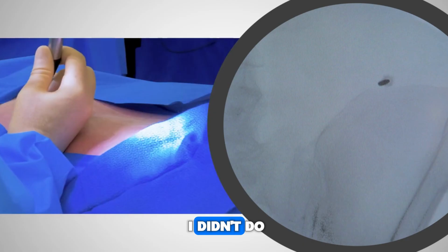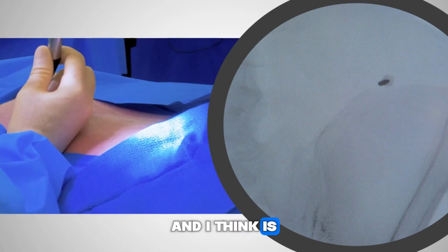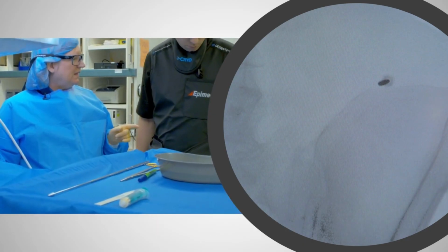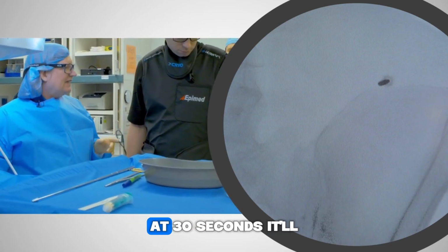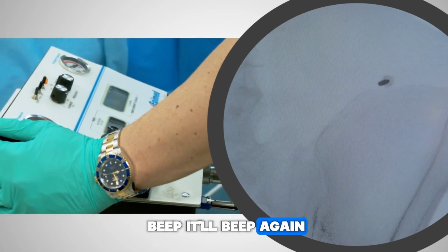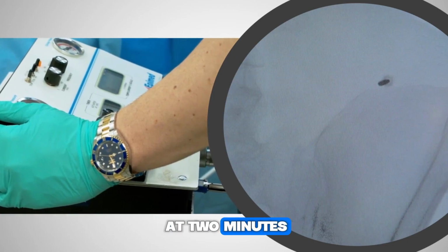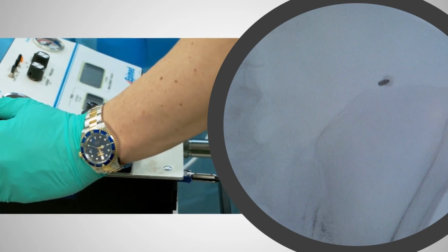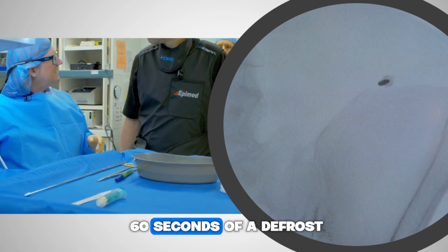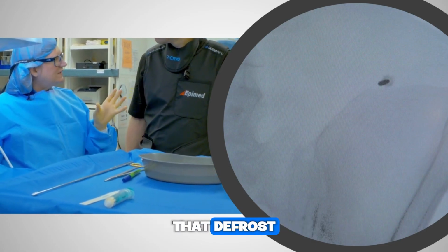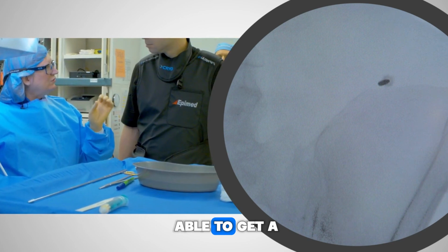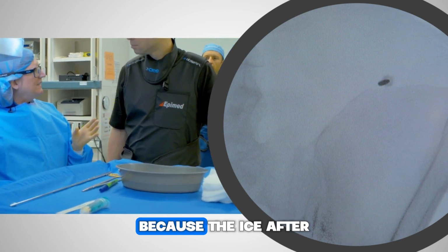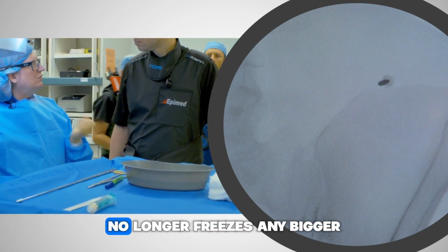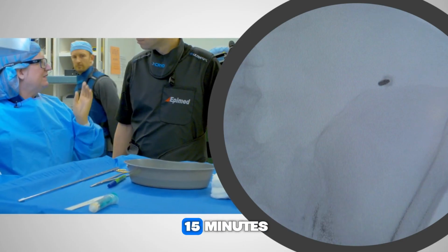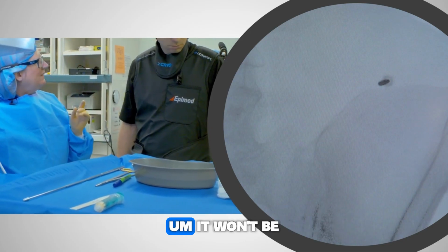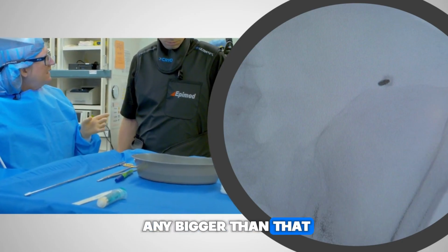Now, the one thing I didn't talk to you about, and I think is an important one, and I'll let you keep on freezing for a minute. At 30 seconds, it'll beep again at 1 minute, at 1 minute 30, at 2 minutes. I usually do a 2-minute freeze, and then 30 to 60 seconds of a defrost. That defrost allows you to get a bigger ice ball, because the ice after about 2 minutes no longer freezes any bigger. You can freeze for 15 minutes, there's that beep. It won't be any bigger than that.